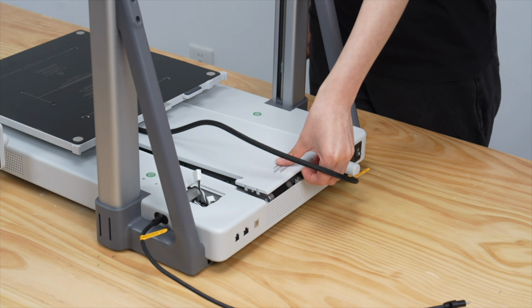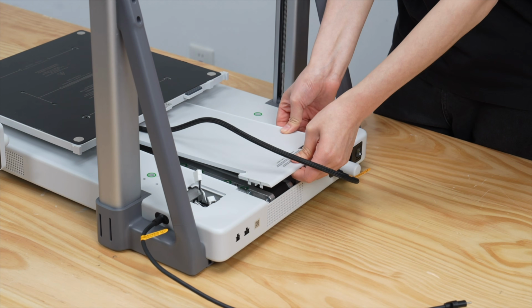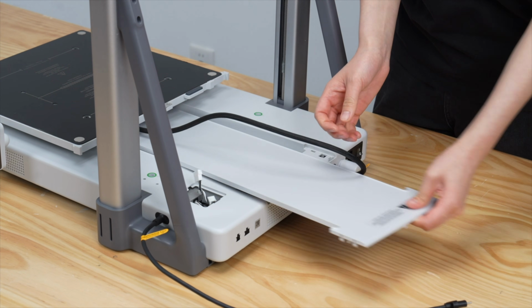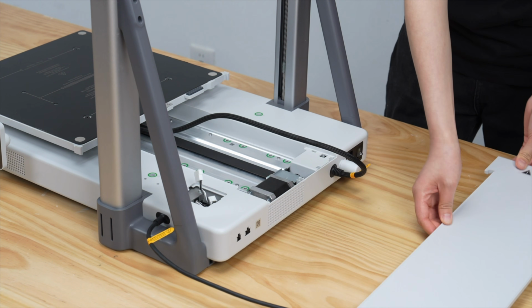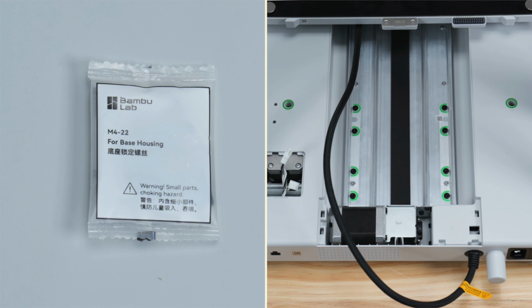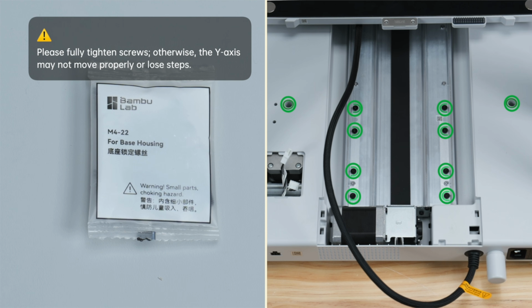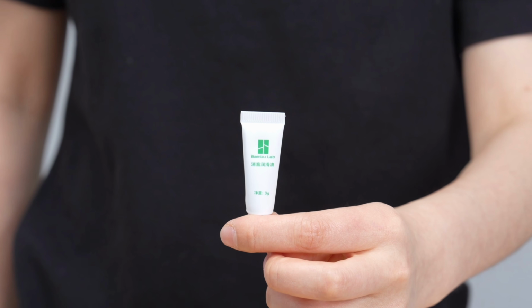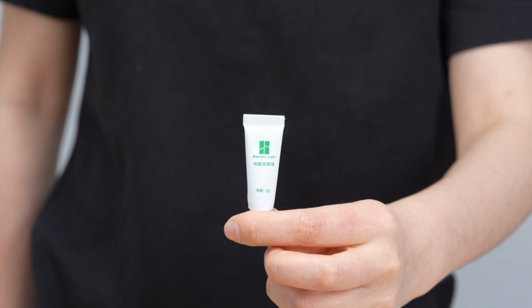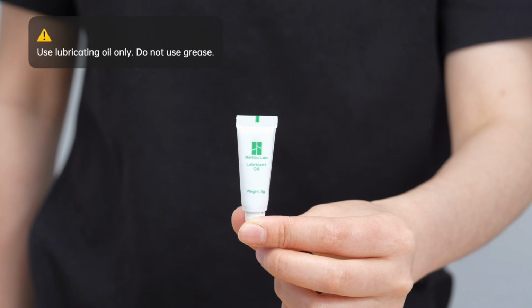Lift the rear of the Y-axis top cover upward and gently remove it. Next, using the 10 screws from the accessory box and an H2.0 wrench, we will install them into the marked holes. It is important that all base locking screws are fully tightened. Next, take out the lubricant oil from the accessory box. Important, we must use lubricant oil only.